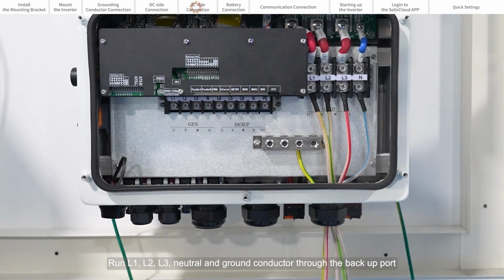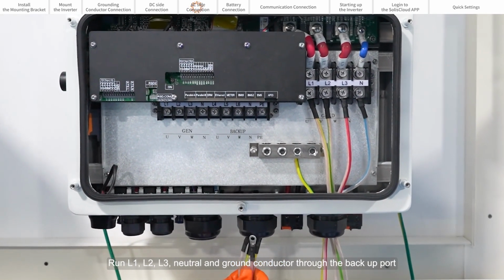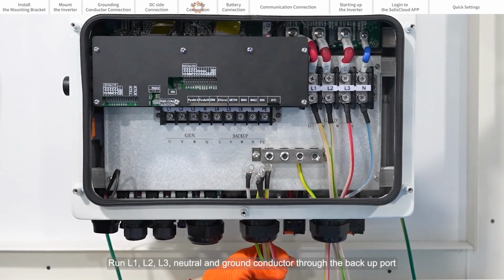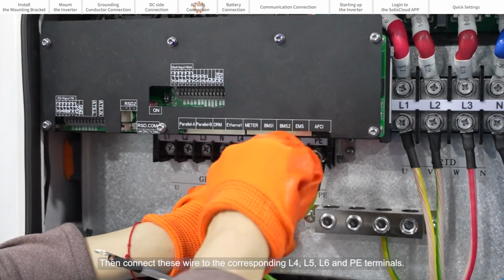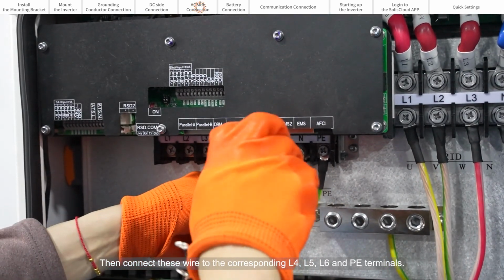Unscrew the backup terminals. Run L1, L2, L3, neutral and ground conductor through the backup port. Then connect these wires to the corresponding L4, L5, L6 and PE terminals.